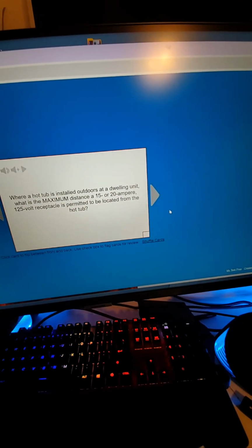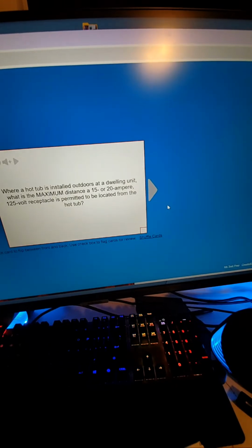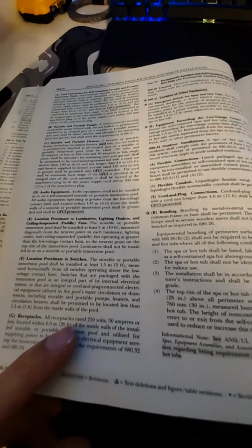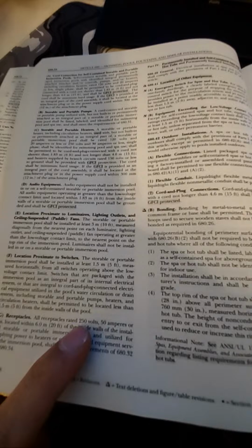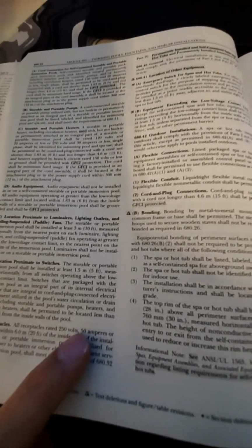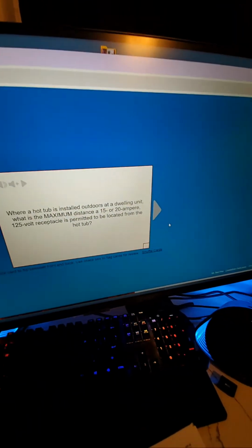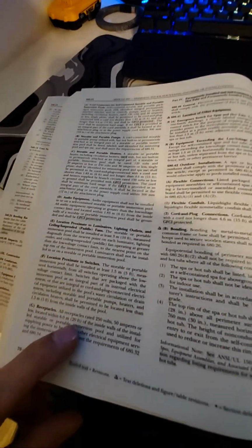What does it say here? It's outdoors, maximum distance of a 125 volt, 20 amp, 125 volt receptacle. So 250 is more than 125. 50 amps is more than 15 or 20. So therefore, this is your answer here. It's going to be 20 feet. All right, there. Let's see. 20 feet. There you go.